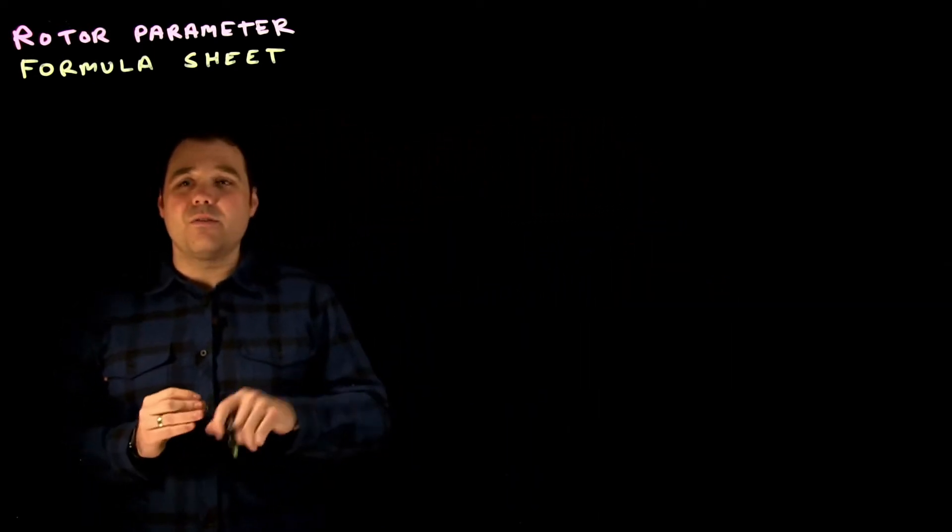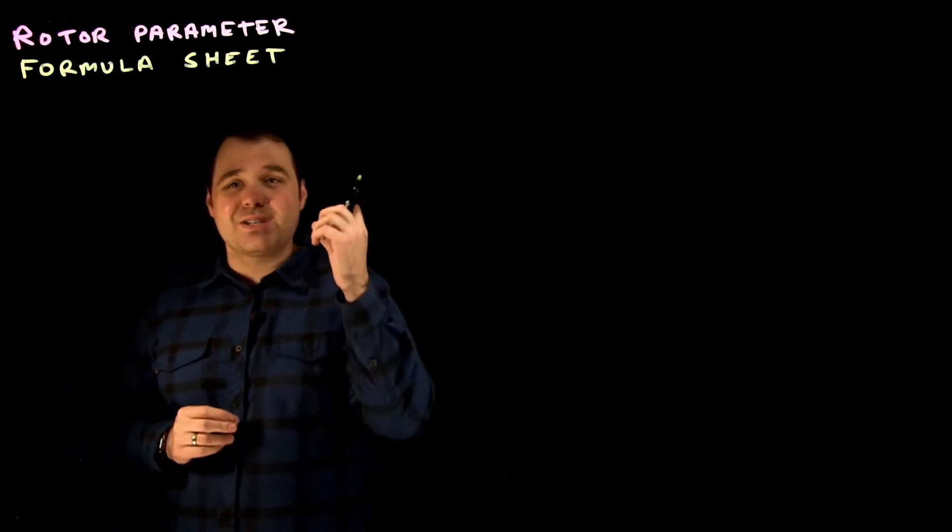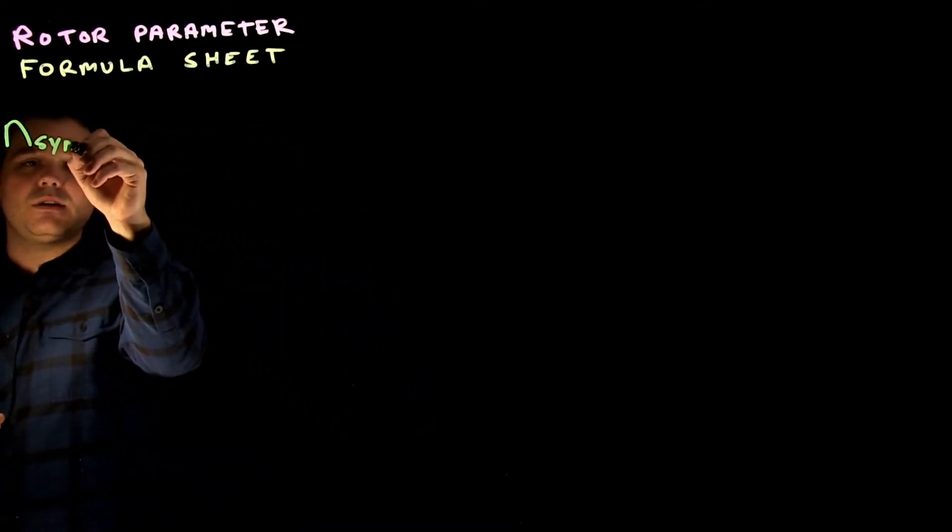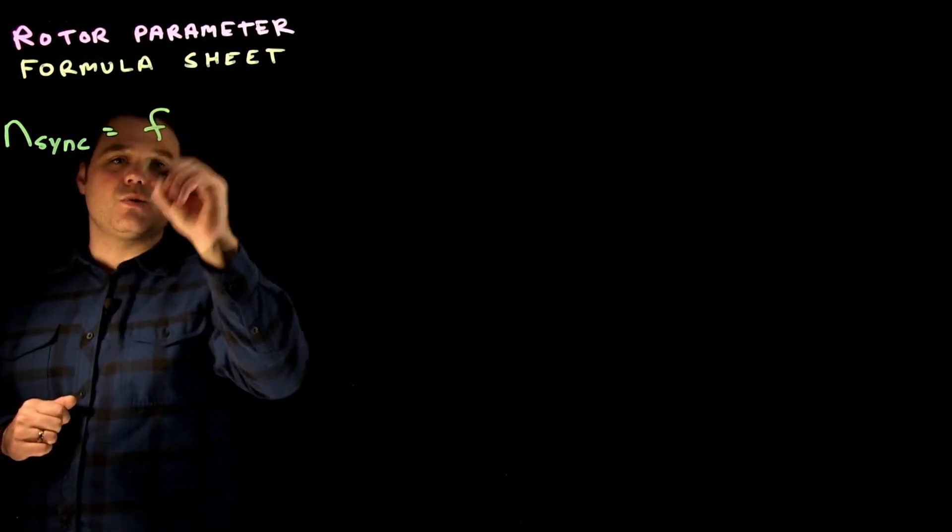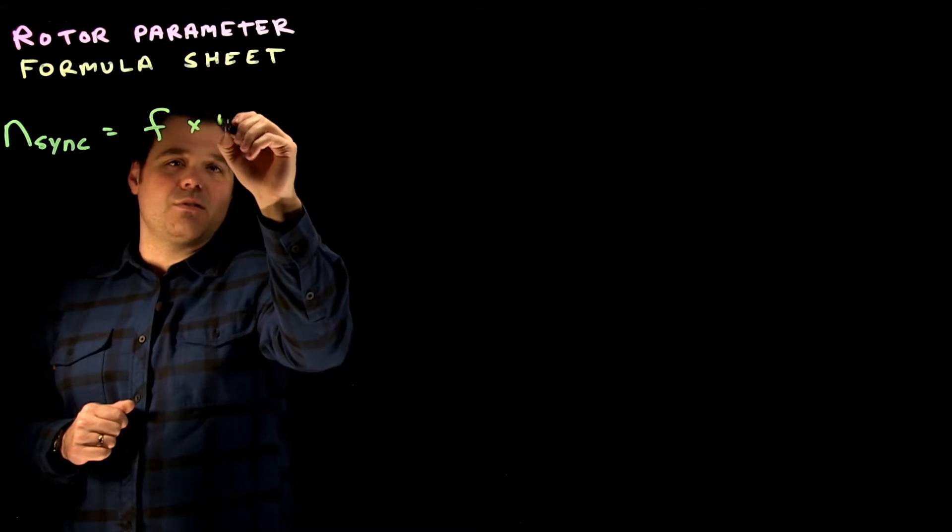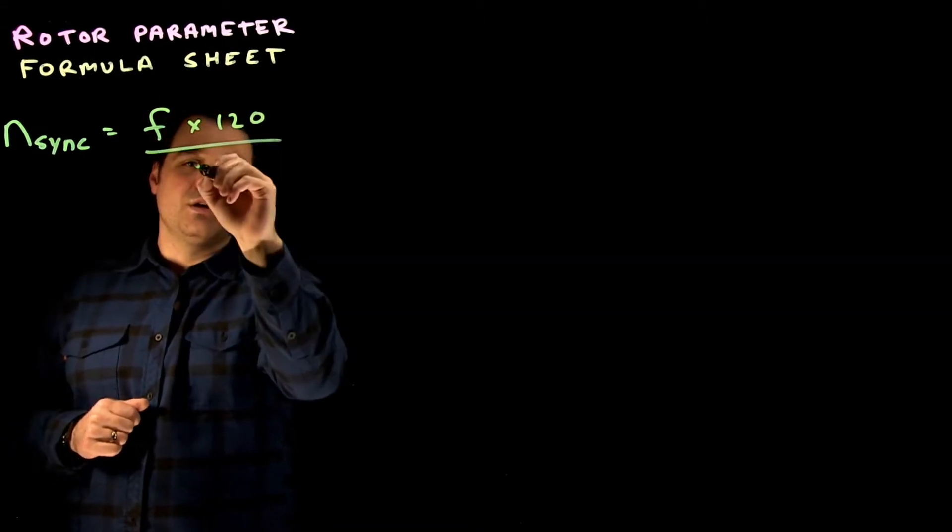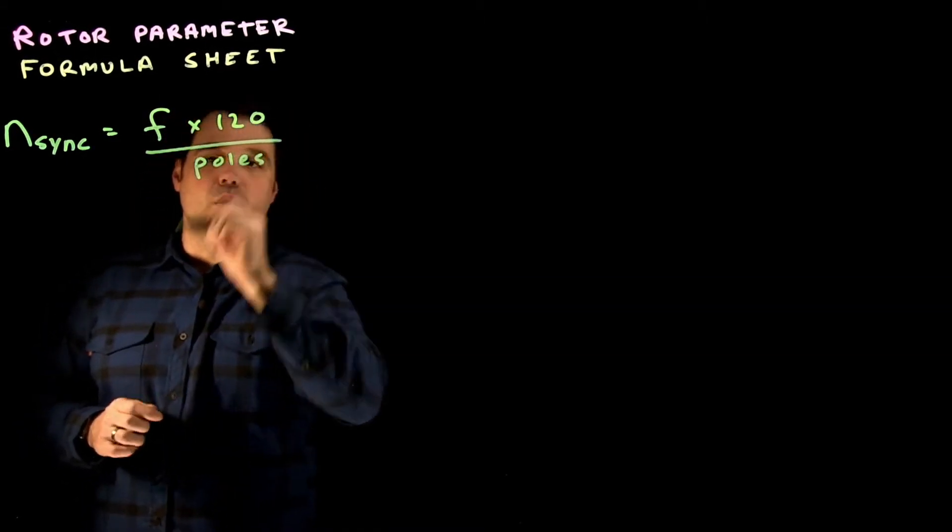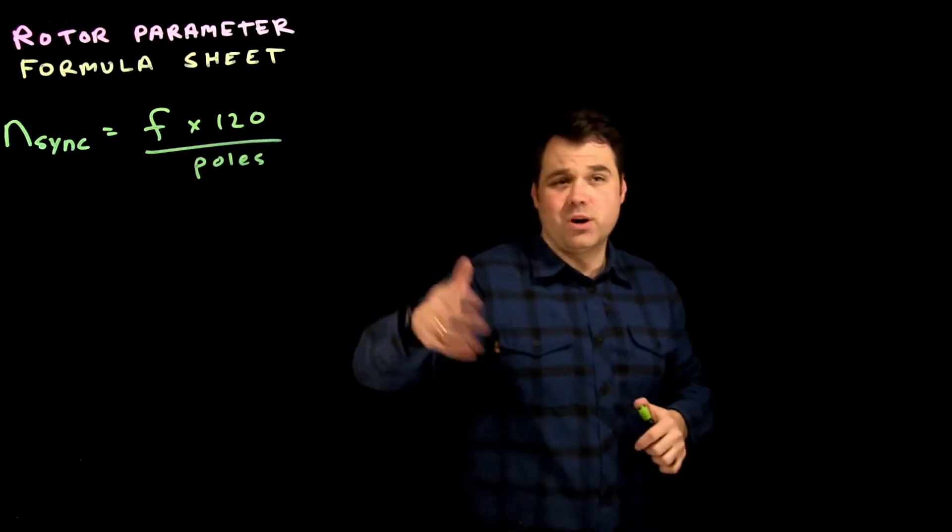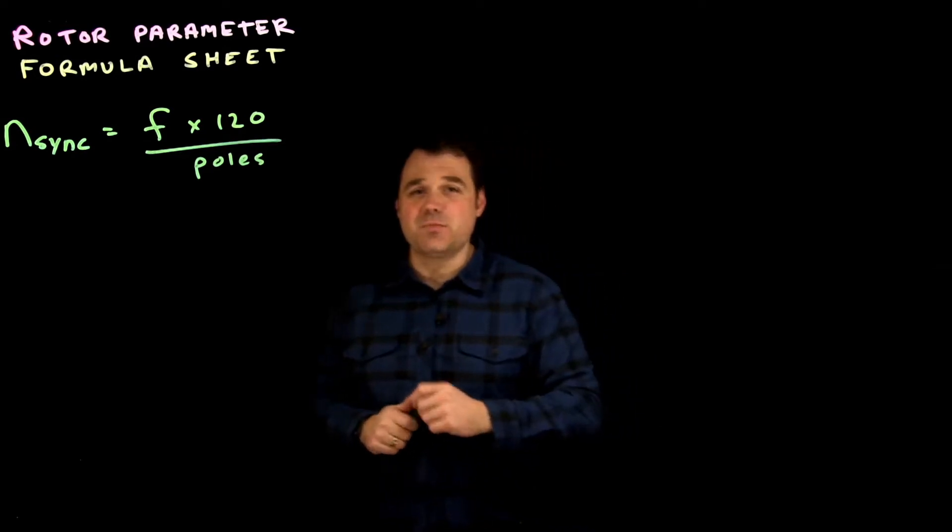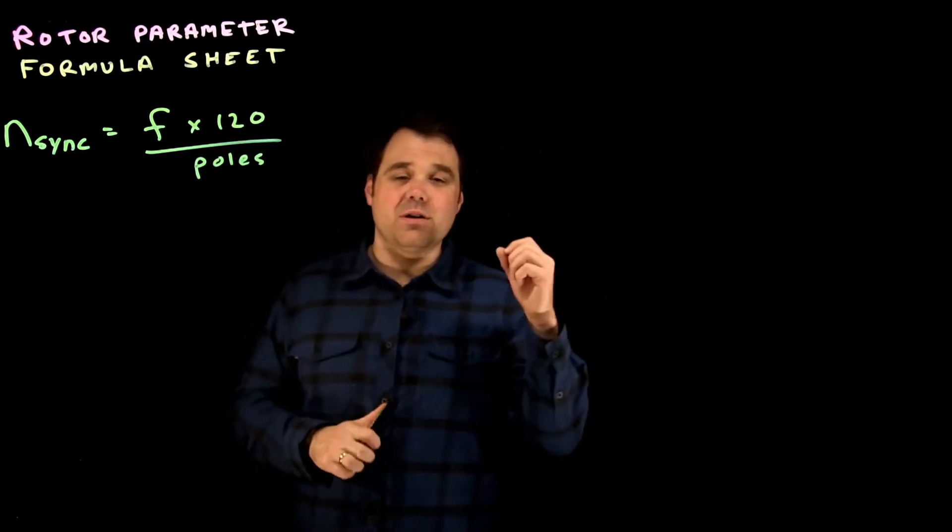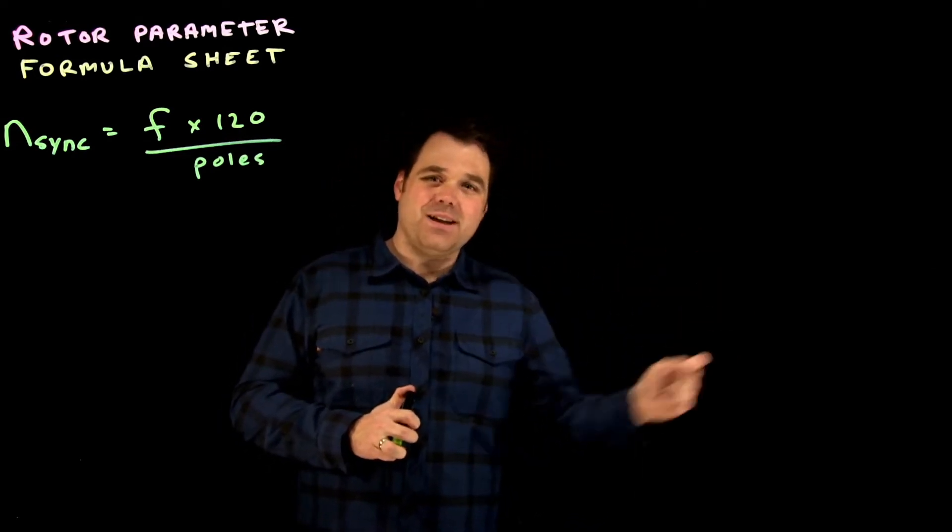So first up, a really important thing when it comes to rotor parameters is our synchronous speed. Synchronous speed is the speed of the rotor, right? We can get that by taking the source frequency, 60 hertz here in North America, times 120 divided by the number of poles. So 60 times 120, it's a four pole motor divided by four equals 1800. Perfect. Synchronous speed - speed of the rotor or stator rotating magnetic field.